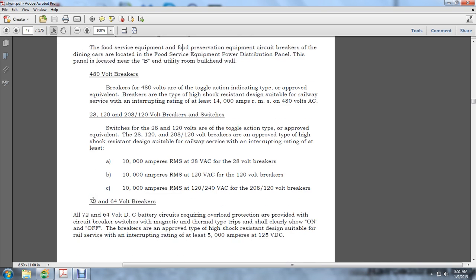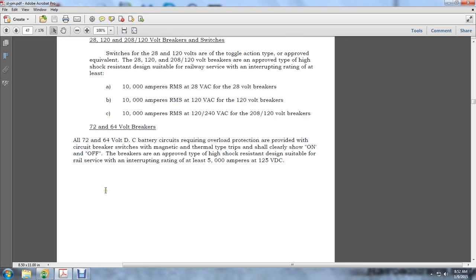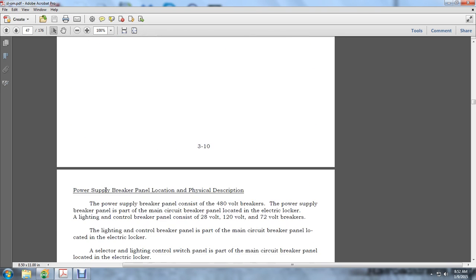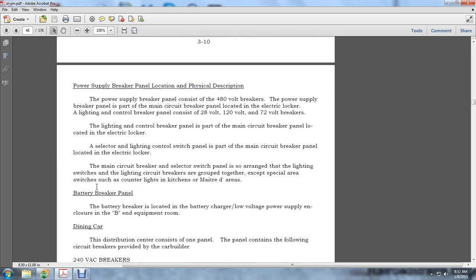The 72 and 64 volt breakers. All 72 and 64 volt DC breakers require overload protection provided by circuit breaker switches with magnetic thermal type trips, and shall clearly show on and off. The breakers are of high shock resistant design suitable for rail service, with an interrupting rating of at least 5,000 amperes at 125 VDC.